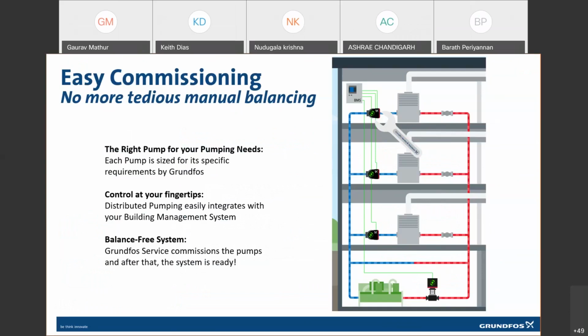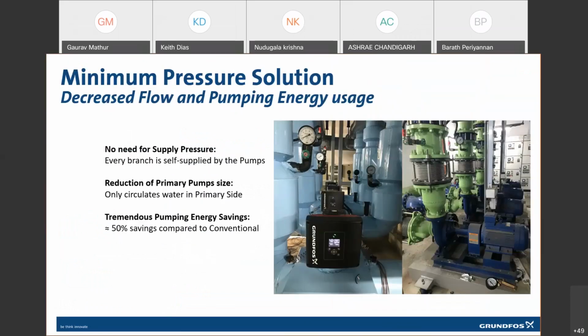Thank you. Okay. So this is what is happening when you are designing the pump as per the exact requirement. The second point, which we have seen as one of the key benefits of distributed pumping, is a minimum pressure solution. That means decreased flow and pumping energy usage. You have seen that the size of the primary pump has reduced because the head for which it is designed is much lesser compared to the conventional system, since it is now designed only for the friction loss in the plant room. This picture depicts how the pump size has reduced from a much bigger pump to a much smaller pump.